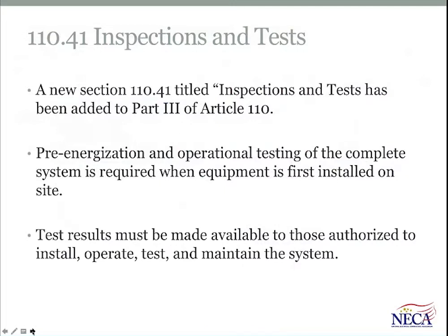110.41 is not new information to the code, but it's an expansion. If you want to write down section 225.56, for outside feeders and branch circuits, inspections and operational testing was required for medium and high voltage circuits and equipment. What's happened this cycle is a new section 41 has been added to part 3, which deals with those medium and high voltage installations of feeders, circuits, and associated equipment, and a requirement for pre-energization and operational testing of the complete system. And that's something that's industry practice.